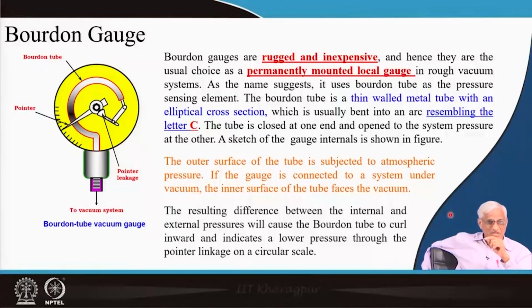For example, in refrigeration compressors you will have these gauges. If you carefully observe a refrigeration network, you will find the plus side measures the freon pressure, but the minus side is also there. Normally we never see that indicator, but during maintenance, when they evacuate and refill, the signal shows minus. That minus means with respect to atmosphere, it is minus. During that time, it is acting as a vacuum gauge.